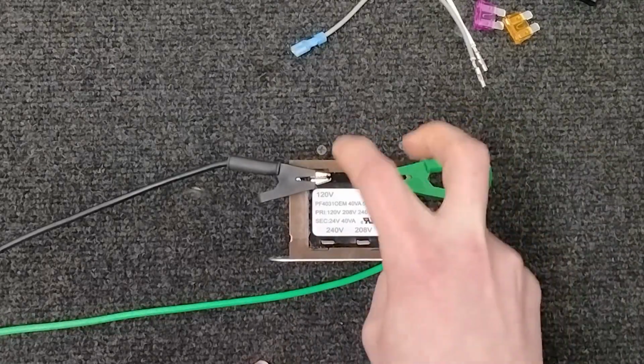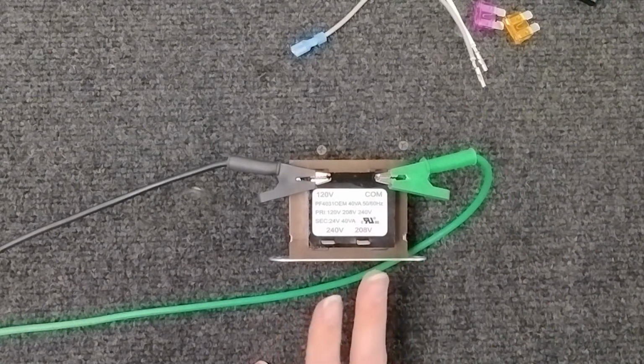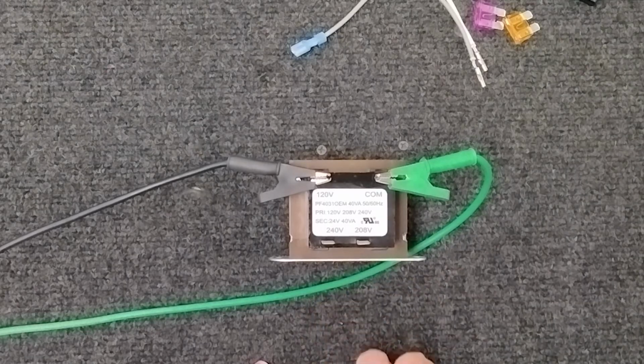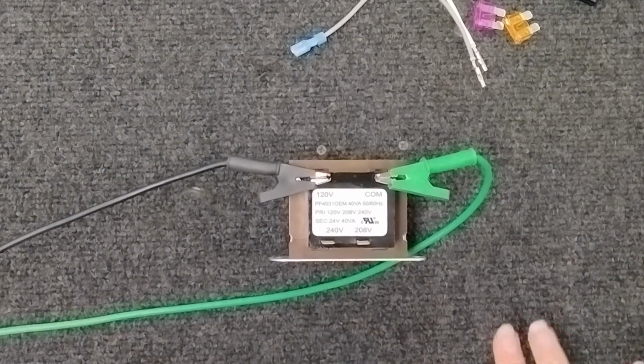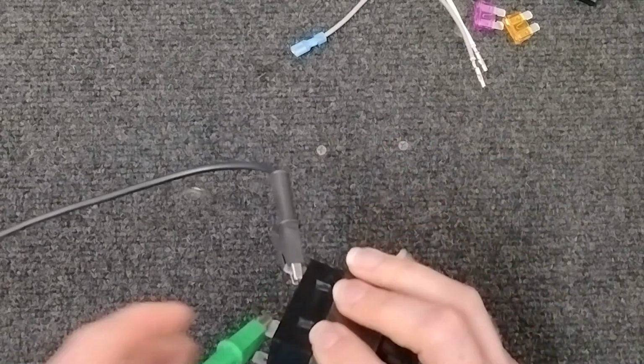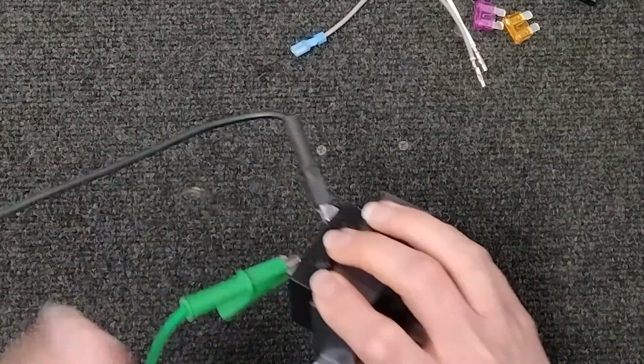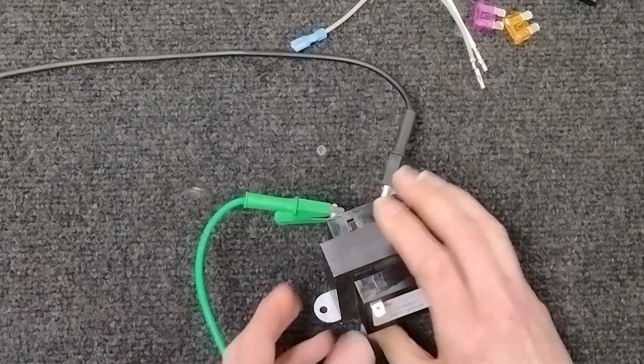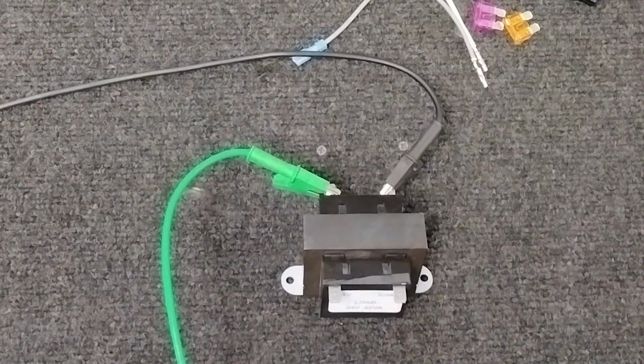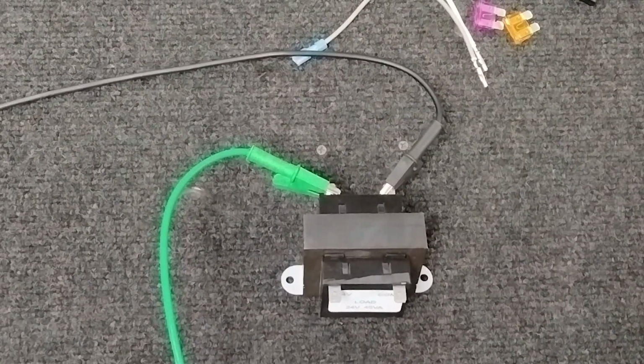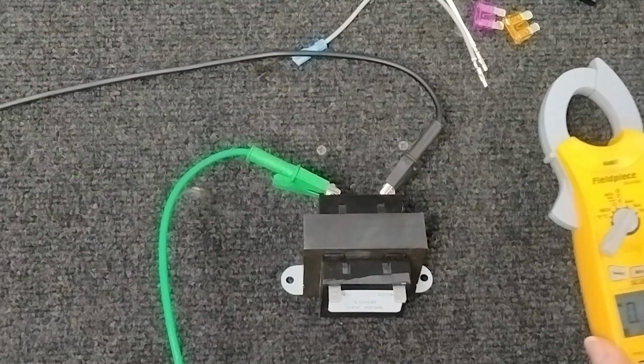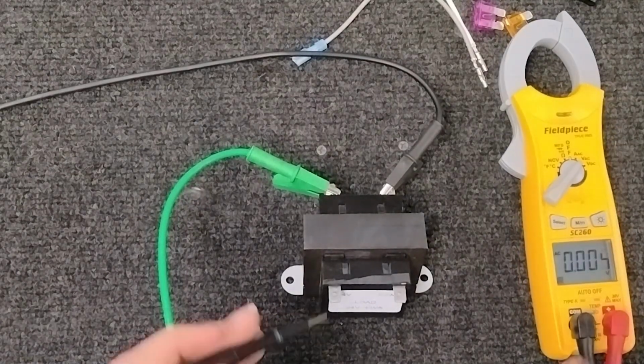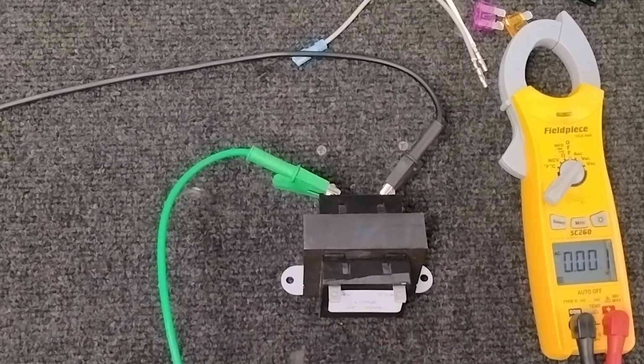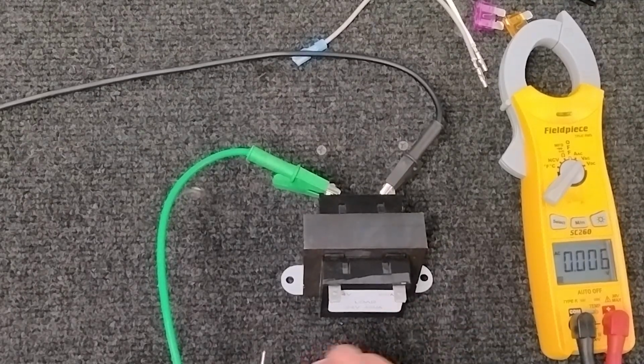So once you know you are getting your high side power, we then need to know if your transformer is putting out your 24 volts to the low side power. Because if that doesn't send out your 24 volts, of course nothing is going to come on. All of that's going to run off of that 24 volts AC. So now that we know we've got high side, and again, your 24 volts can also say just load on there. You can say 24 in common, or have both like this one.